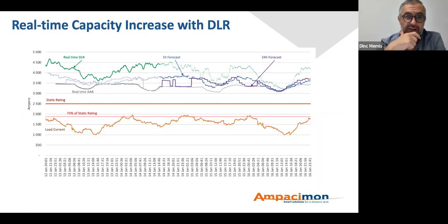On top of that, the green one is the real-time DLR, with the capacity calculation coming from our sensor on the line. We are also able to provide an ahead forecast, between 4 to 6 hours ahead or day ahead. This is just an example from real life that I want to share with you, of how real-time DLR can provide significant capacity gains on existing lines.